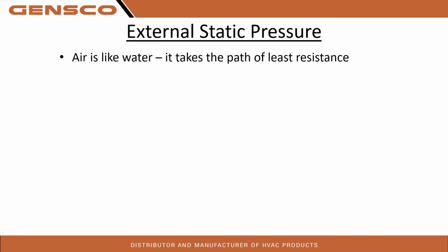Question is, can we use a MERV 13 air filter as a standard filter, or is it better to use a lower MERV? I got a great chart for you, so hopefully you're staying to the end. It goes through actual static pressure and how many CFM per MERV. Air is like water. It takes the path of least resistance. While I'm on that, same with voltage.